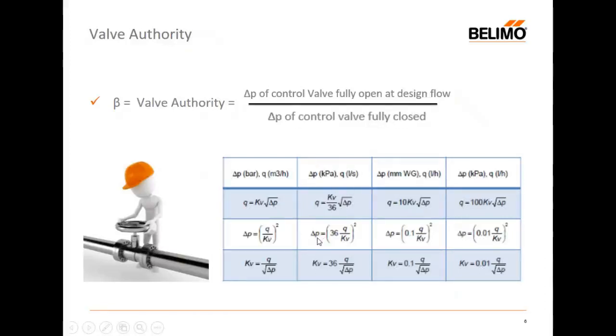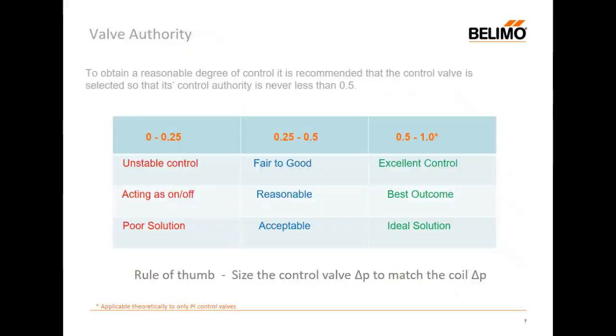And if I need to know the pressure drop of the control valve, then I need to know the design flow and the Kv of the valve I'm going to select. I can get that from the manufacturer. He'll tell me the Kv of the valve. The design flow rate will be calculated according to the heat load, sorry, and we'll understand the delta P. So it's a very useful chart. We use it a lot. We always like to understand the authority of any control valves that we're going to supply. And it's important that we look for good, or at least reasonable, control valve authority.